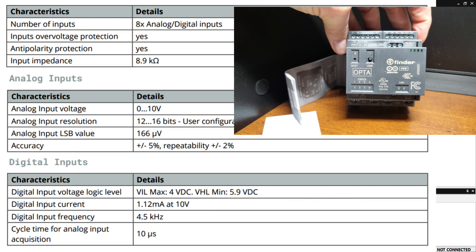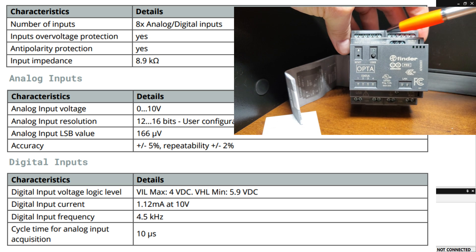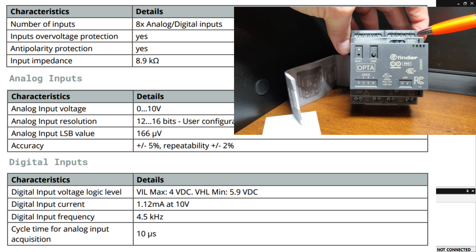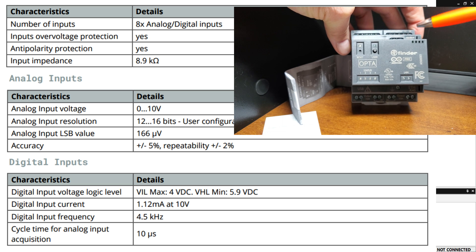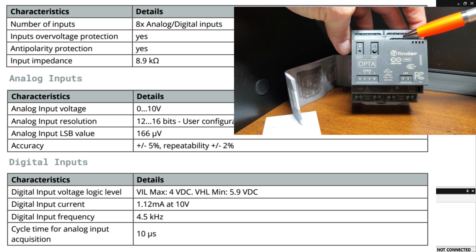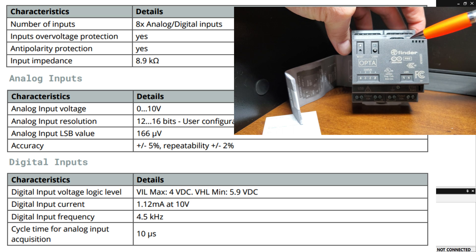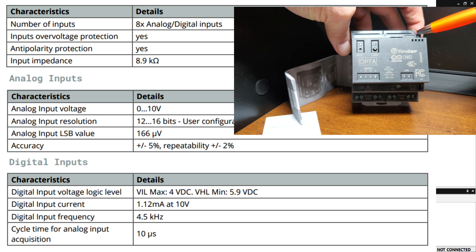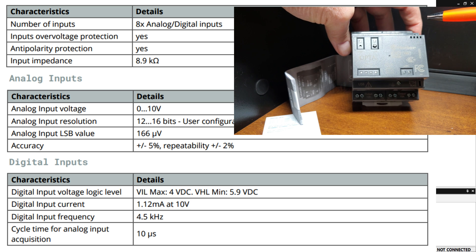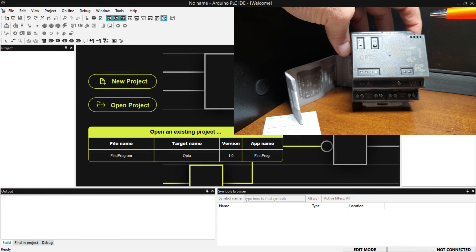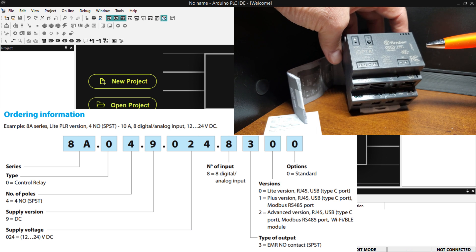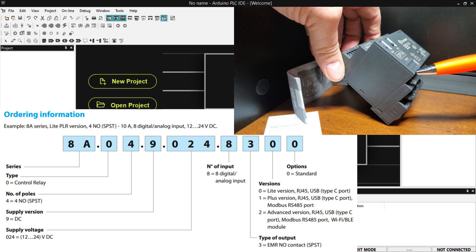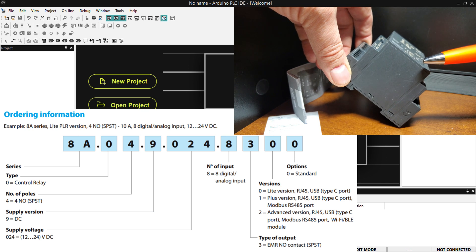Each of the eight inputs can be analog or digital. Analog inputs accept 0 to 10 volts DC at a 12 to 16 bit resolution. Digital inputs will be off at 4 volts DC and on at 5.9 volts DC. Standard industrial voltages of 12 or 24 volts can be used for sensors. The inputs are overvoltage and polarity protected, so you don't have to worry about incorrect wiring damaging the controller.